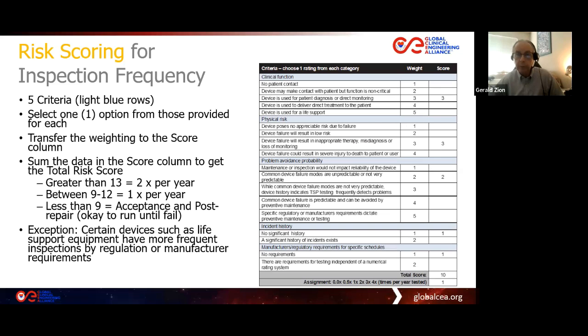And in that case, there will be a use hour indication somewhere on the medical device, either in the user interface, the graphic user interface display, or else it may be an actual hour meter, more electromechanical, and you may find that on the back of them. Way back, the Bourns Bear ventilators had a use hour meter on the back side of the ventilator, and that's how you would determine the use hours. What that meant in that case was you had to know what the use hour meter reading was on the prior inspection. And so you're going to have to manage that.